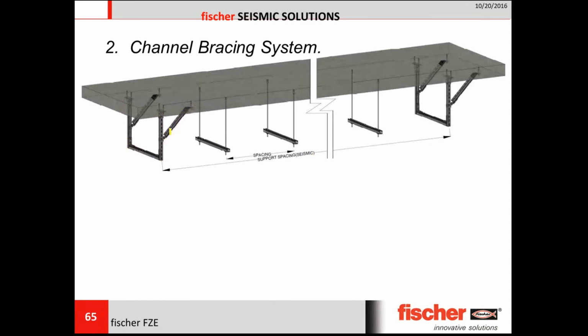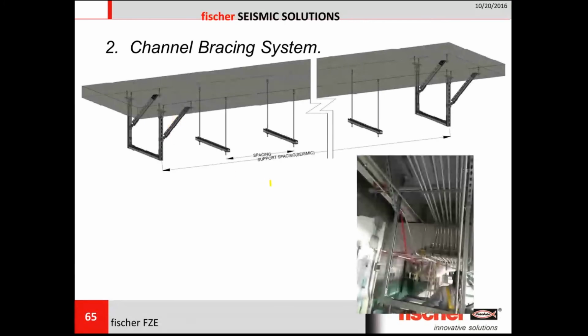Why? To make the system stronger. Why do you need it to be stronger? It needs to be stronger, especially when your service is far away from the ceiling. Let's say you have a drop height of 2 meters, 2.5 meters, then the normal single channel rigid system might prove not to be safe. So you need to additionally strengthen it with additional components to make it stiffer.